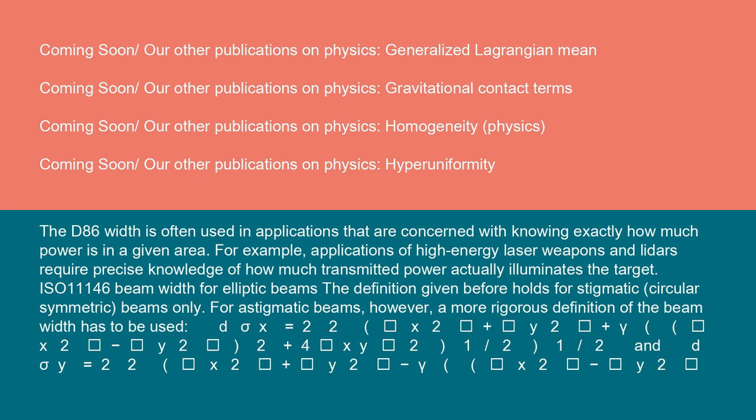ISO 11146 beam width for elliptic beams: The definition given before holds for stigmatic, circular symmetric beams only. For astigmatic beams, however, a more rigorous definition of the beam width has to be used. D_σx = 2√2[√(⟨x²⟩ + ⟨y²⟩ + γ√((⟨x²⟩ - ⟨y²⟩)² + 4⟨xy⟩²))]^(1/2)